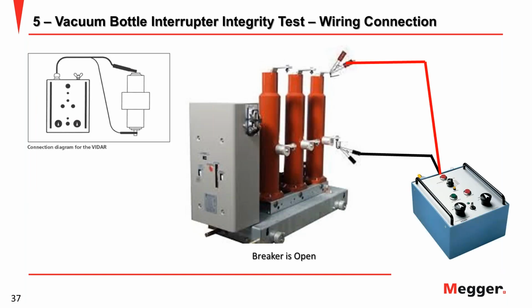This is the circuit connection, a very simple connection. You can test pole by pole, with 2 cables from the test equipment connected to each terminal of the vacuum breaker.